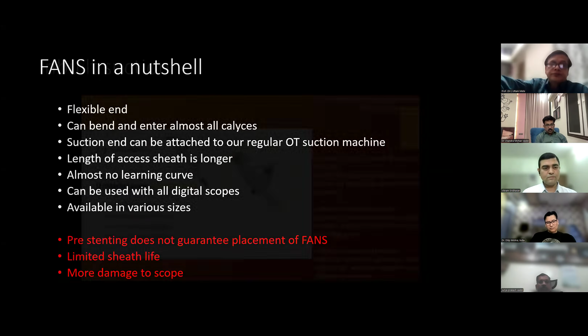Coming to the FANS, the flexible sheath has a flexible end. The access sheath has a flexible end. It can bend and enter almost all the calyces. The suction end can be attached to our regular OT central suction or to any suction machine. The length of the access sheath is longer than the regular access sheath that we use. Almost no learning curve, except that when we introduce the access sheath, we have to be a little careful not to injure the calyces. It can be used with all the digital scopes.